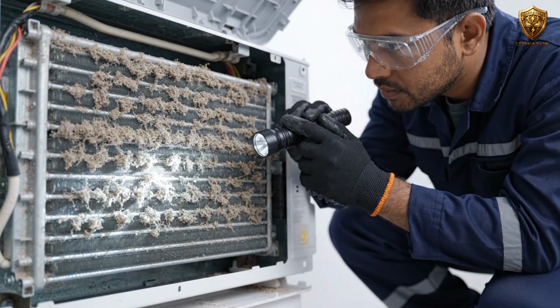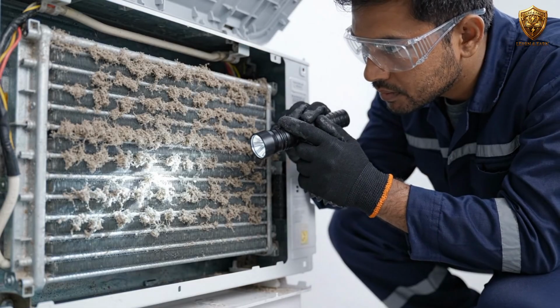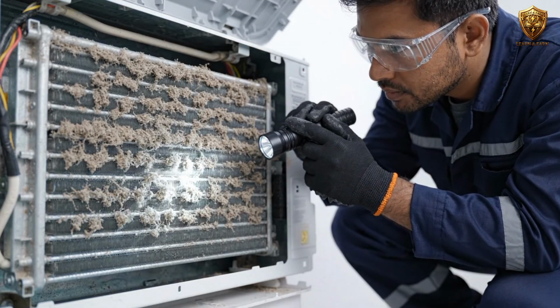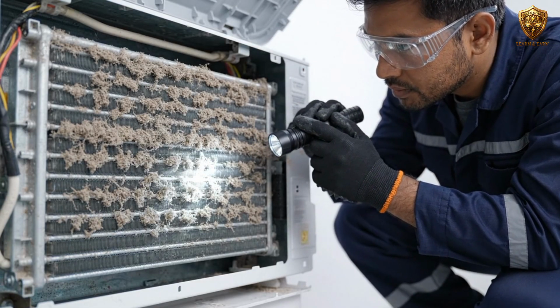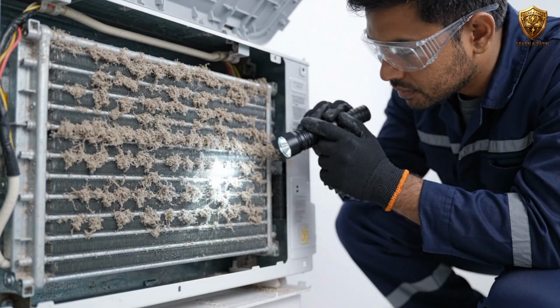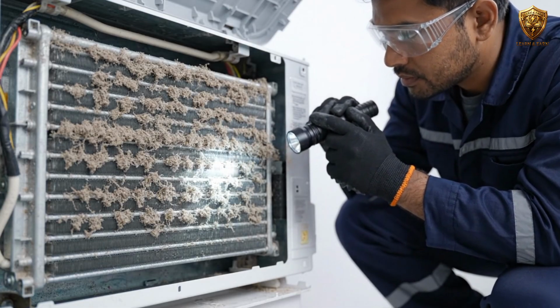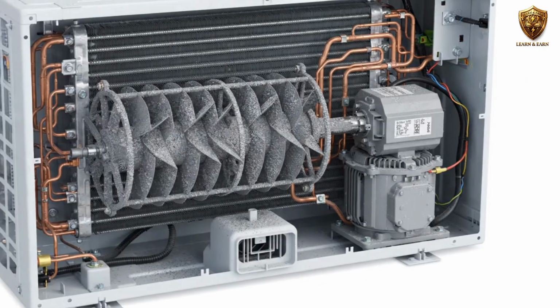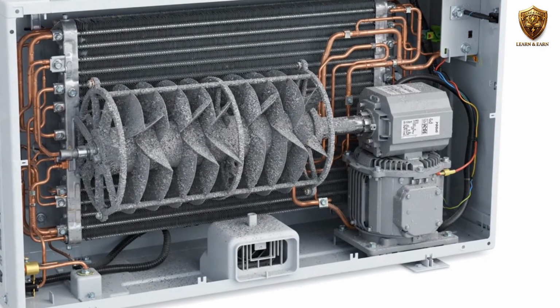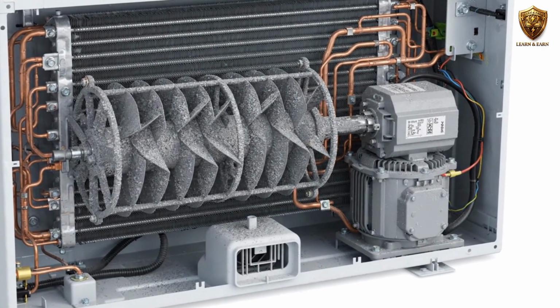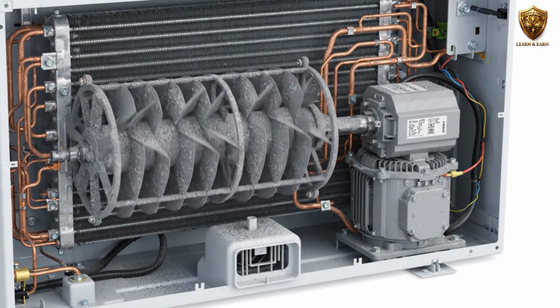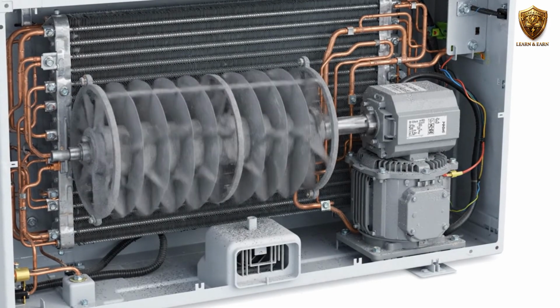This is why the technician needs more evidence before deciding what caused it. Also inspect the indoor coil condition without damaging the fins. A thick layer of dirt can reduce heat transfer and restrict airflow. The blower should also be checked when access is available and safe. A technician should never assume that a visible dirty filter is the only problem.